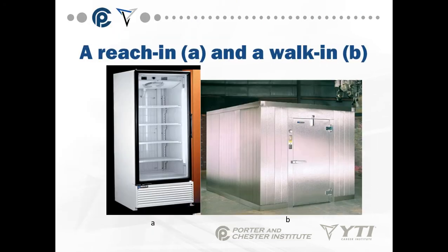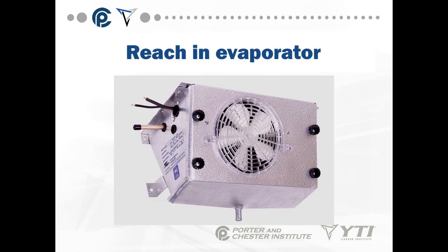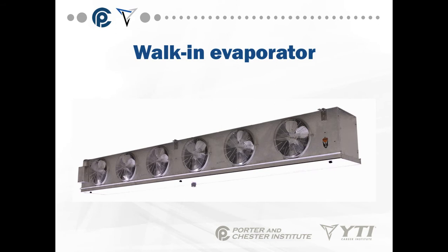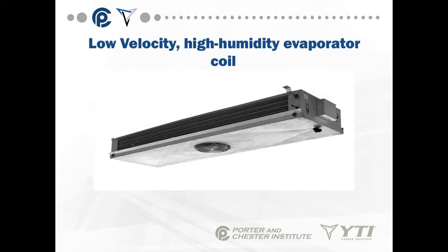For a reach-in evaporator, the standard temperature difference is 20°F. For a walk-in evaporator, it's 10°F. These are the industry standard numbers you really should know. For a low-velocity, high-humidity evaporator coil, the temperature difference is 8°F.